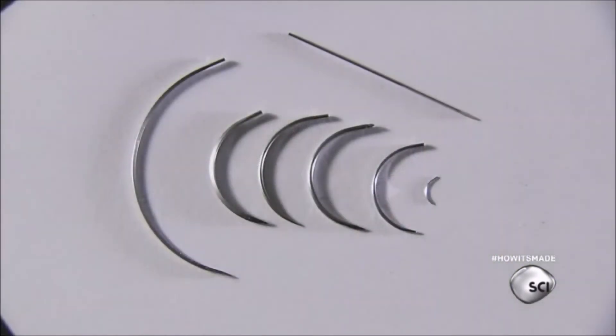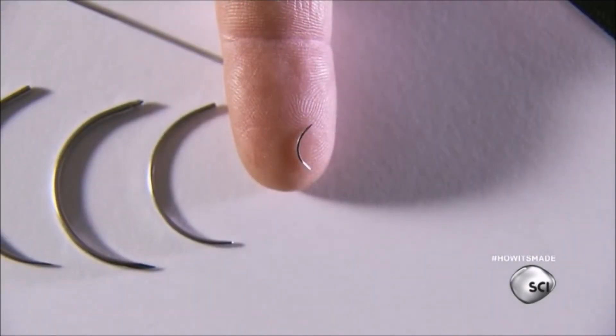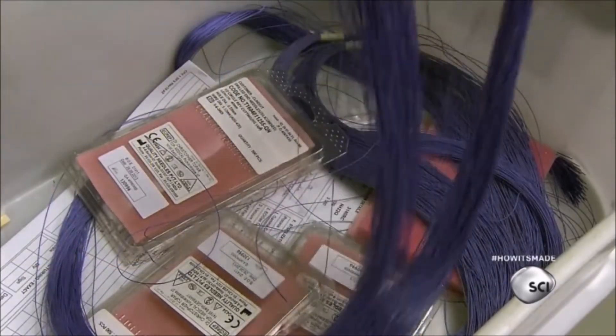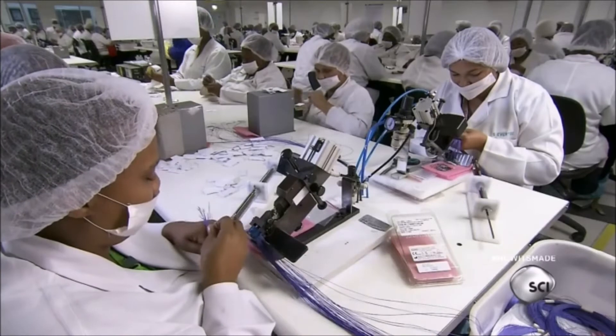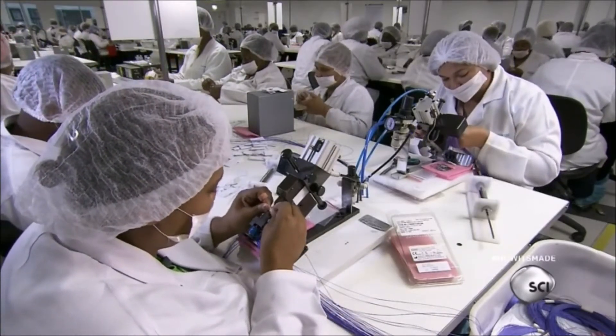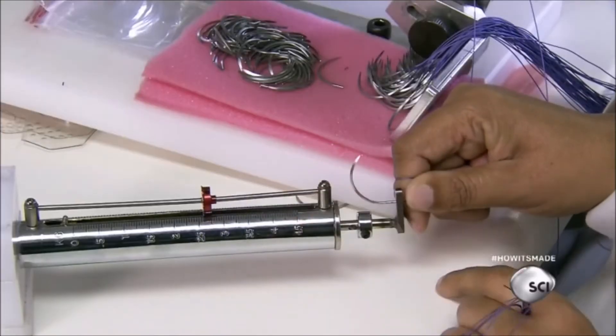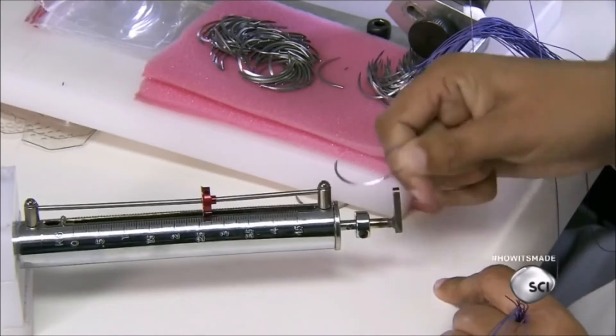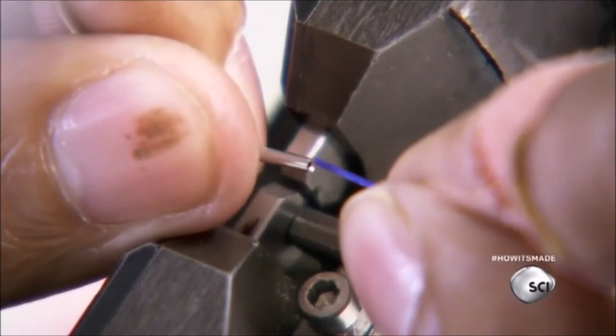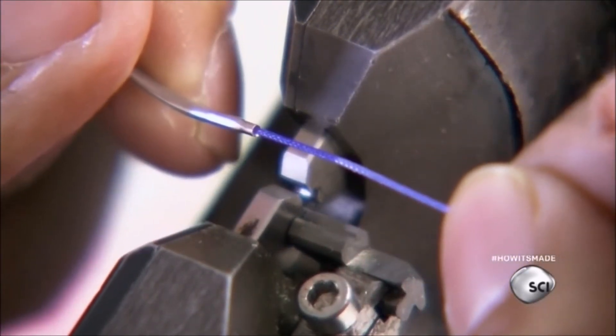Sutures use needles of various shapes and sizes, the smallest ones being 10 millimeters in length. On the main production floor, dozens of workers attach needles to the threads, making sure the attachment meets the suture's requirements. The operator inserts the glue-hardened end of the thread into the back of the needle and crimps it tight with a mechanical swaging machine.